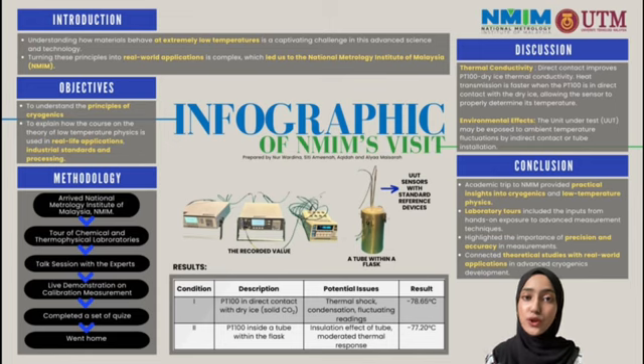Eventually, we proceeded to the auditorium to observe the calibration measurement of cryoliquid demonstration. An experiment was conducted by testing a unit under test consisting of PT100 under two distinct conditions with the standard reference. This experiment was set up by filling an insulating flask with dry ice, which maintained a temperature of approximately negative 79.65 degrees Celsius. This setup provides a consistent low temperature environment ideal for this experiment, and the PT100 sensors were placed under two different conditions, and the table shows the different condition setups of PT100.